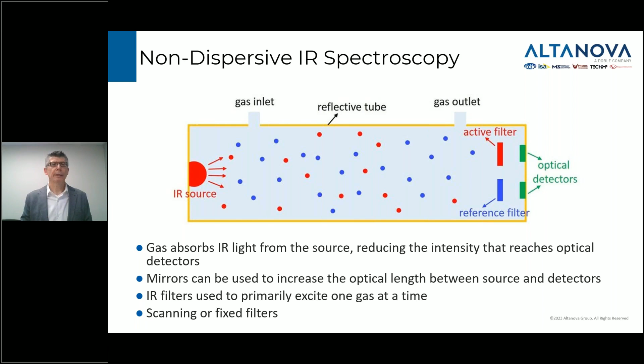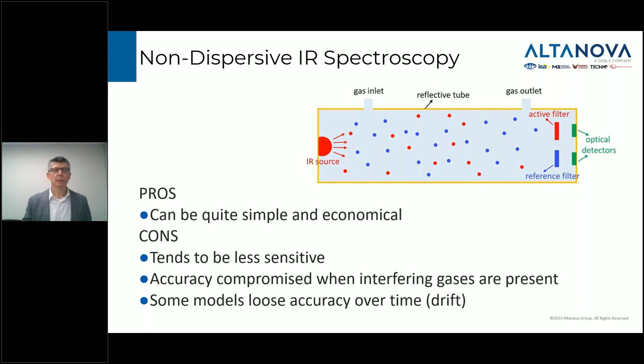Some advantages of the NDIR approach are that the hardware can be quite simple and economical. On the downside, it's challenging to make these systems as sensitive as might be needed in the application. There are tricks to improve that. Like all the IR methods, because of the overlaps I talked about in the spectra, when there are interfering gases and compounds present in the oil, that can lead to inaccuracy in the readings. So that's a challenge in general for the IR methods. And some models have been known to drift, losing their accuracy slowly over time.